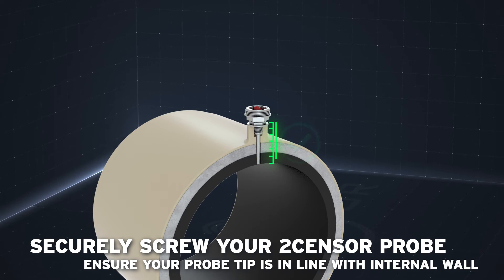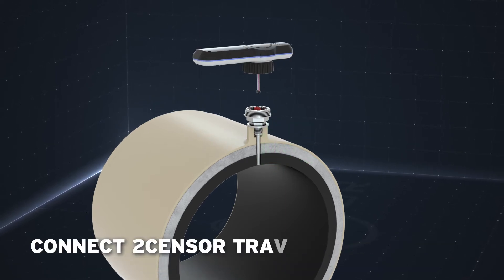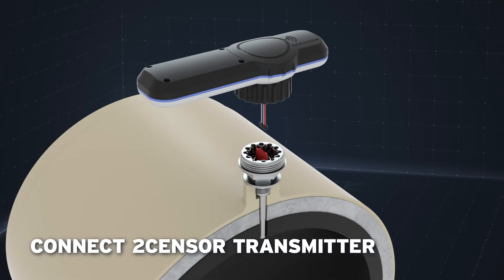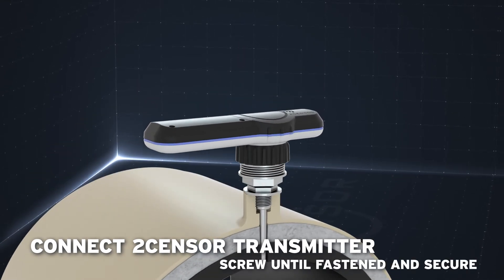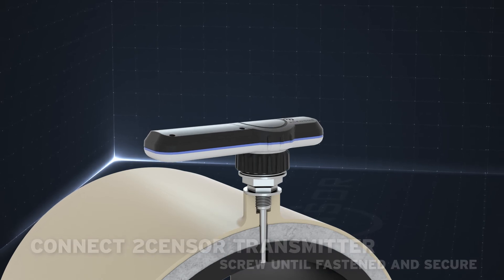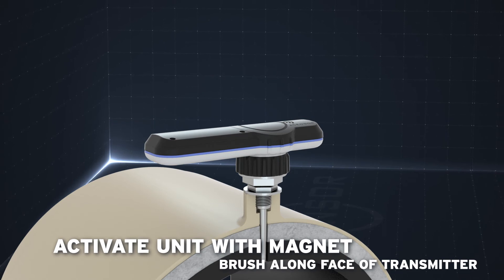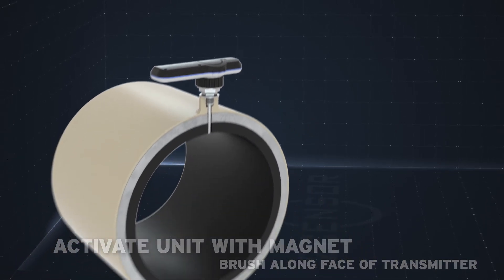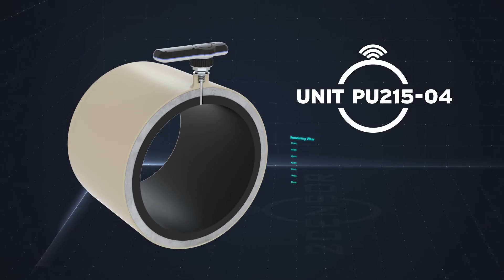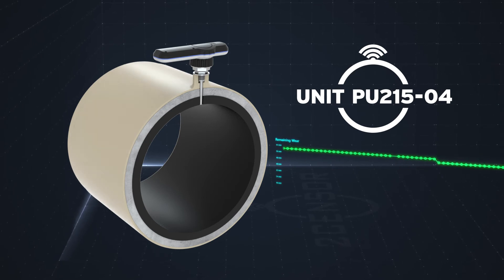Ensure your probe tip is installed to a depth that will finish even with the internal wall lining. Align the cable in the top of the 2Censor transmitter with the corresponding plug in the node and clip together. Screw until fastened and secured. Brush a magnet along the face of the transmitter to activate the unit and you will hear a beep, confirming that the unit has been switched on and enabled. Shortly after, the unit will appear on your dashboard software and you can monitor the status of this pipe at any time.